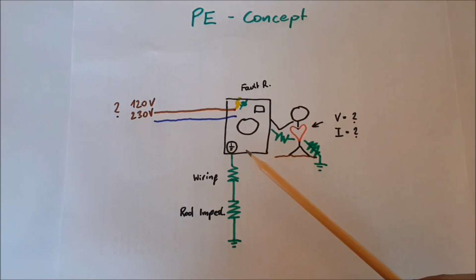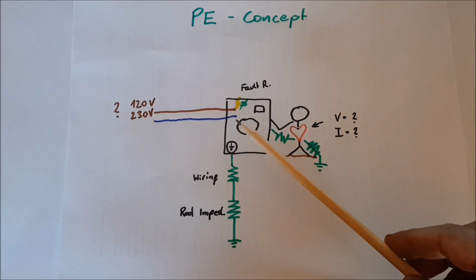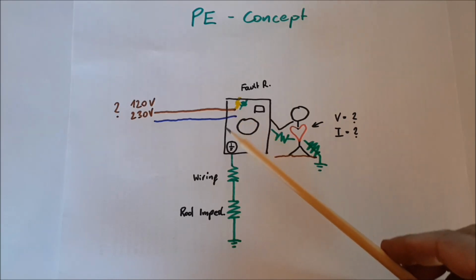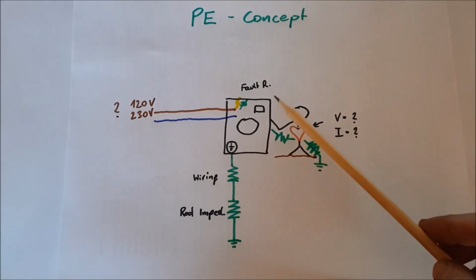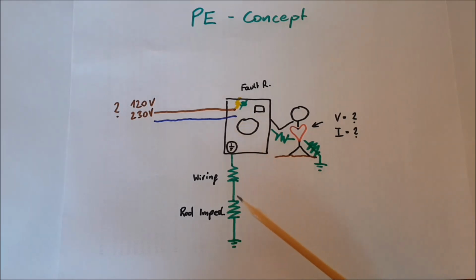Let's say this is a washing machine, a class 1 appliance. We have line and neutral coming in, and a protected shell around it, which is connected to our PE wire and then of course to ground somewhere.